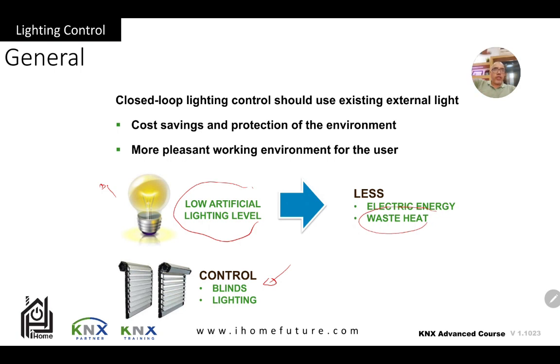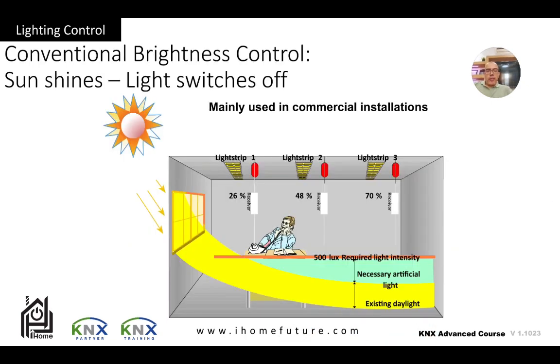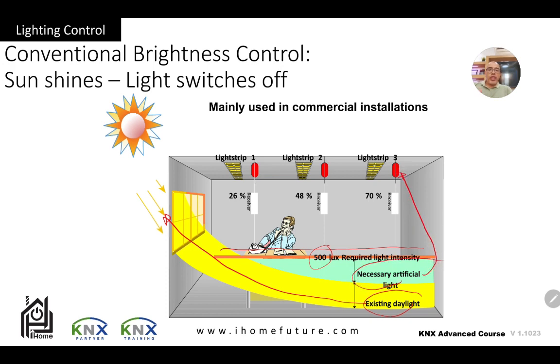We can control the level of light coming into the building. If blinds are down, less daylight enters the office. We achieve this through something called constant lighting. By constant lighting, I want to achieve a specific amount of light reflected on my desk — in this case 500 lux. This is done partly via daylight coming from the window and partly by compensating with artificial light from the lamp.